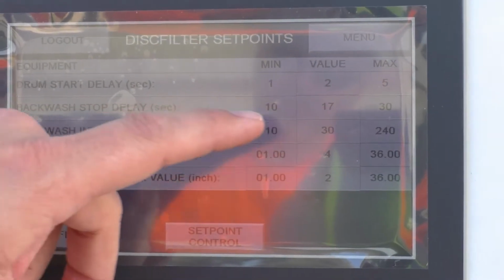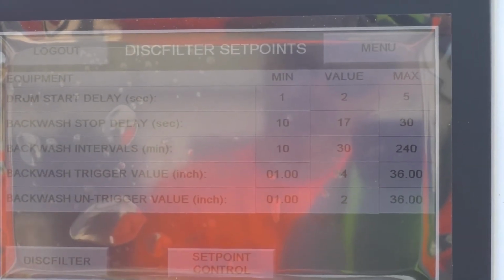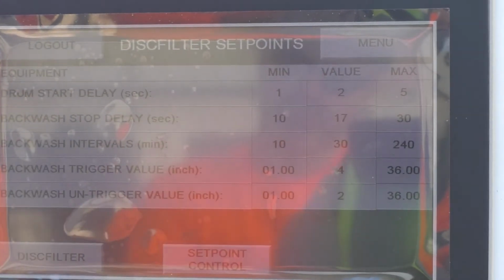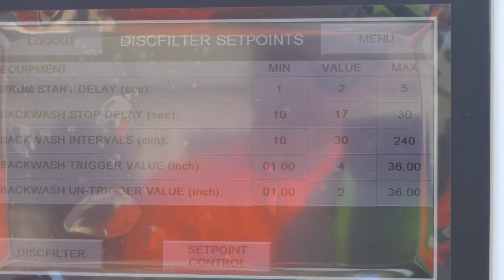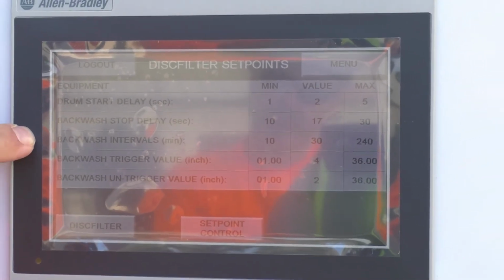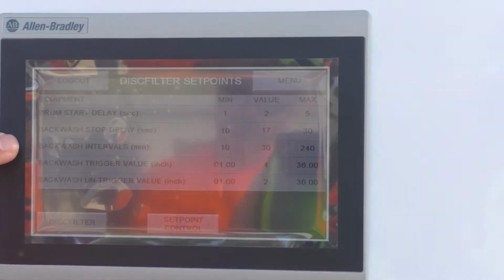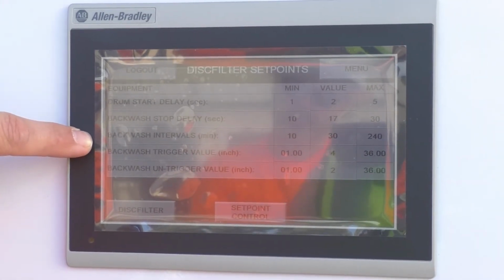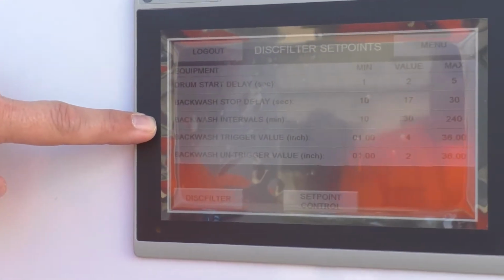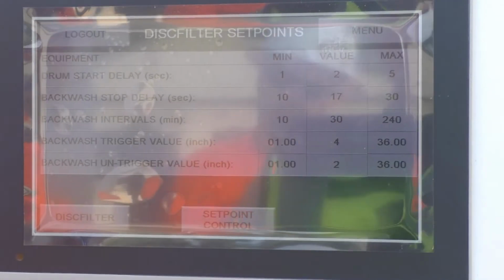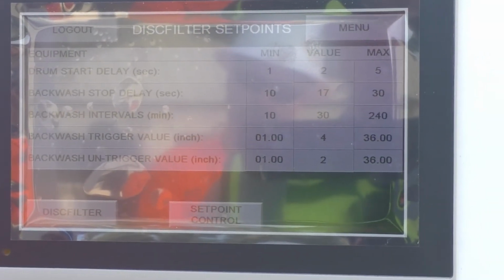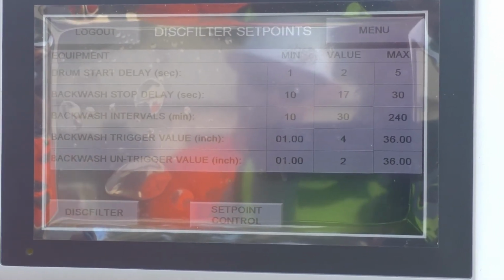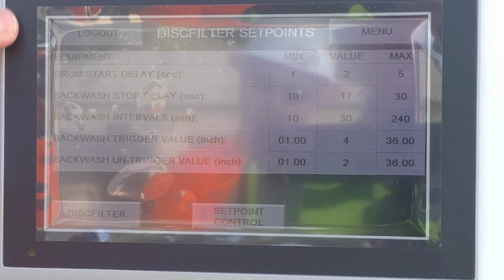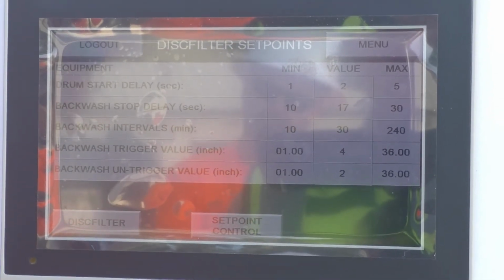Drum start delay is set at 2 seconds. Backwash duration is 17 seconds. And backwash interval automatic timer is 30 minutes. So basically, what this automatic timer means is that at any point within 30 minutes after a backwash, whether it's based off level or the computer itself, it's going to do a backwash. Like I said, these should be the exact same thing as what's on the old unit.